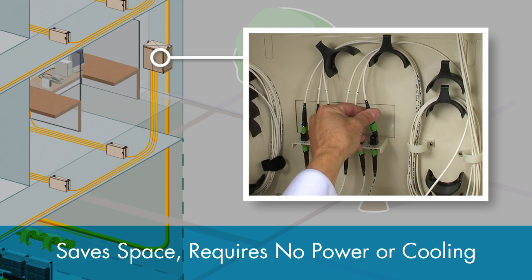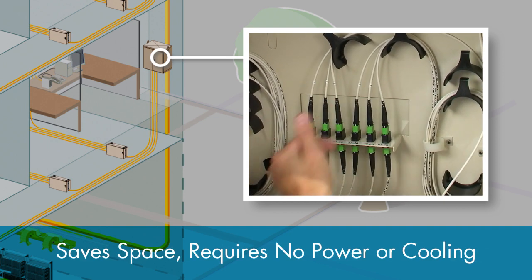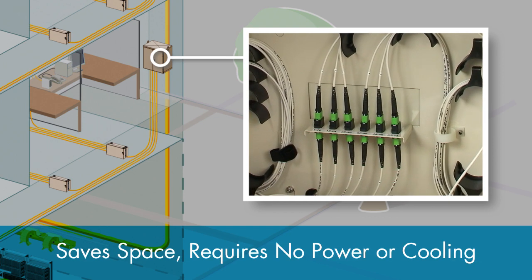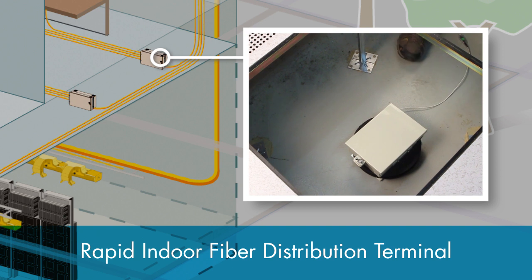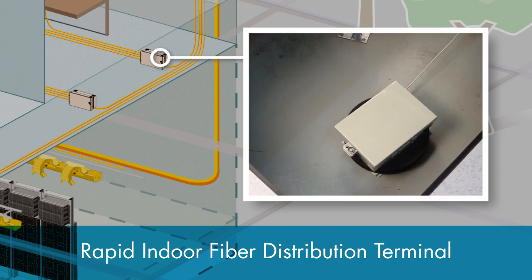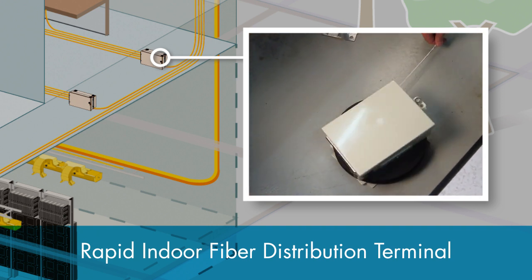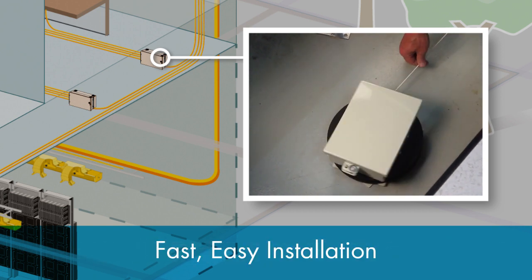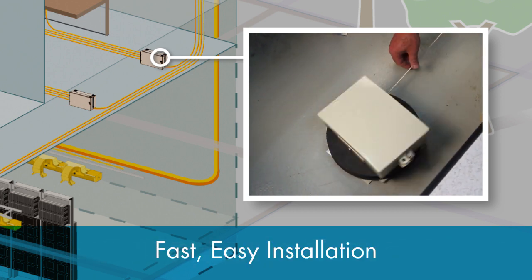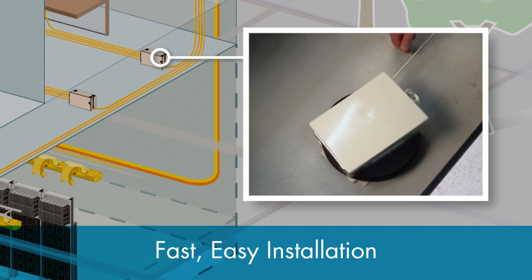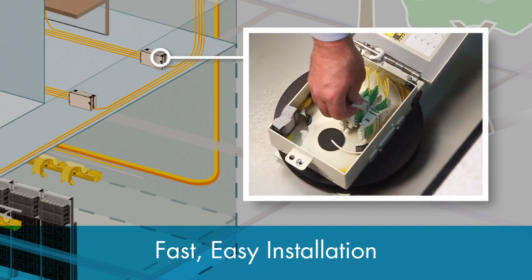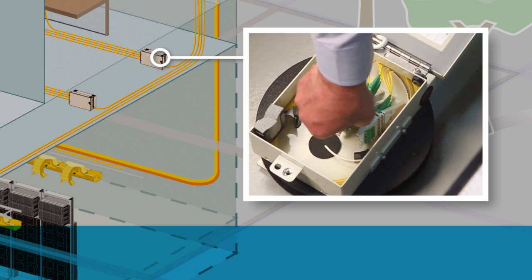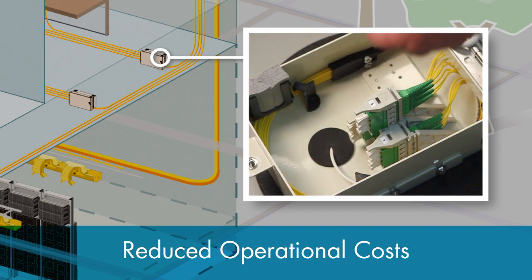It is also wall-mounted, which saves valuable floor space in the IDF telco closet and requires no power or cooling. Optical LAN installations use CommScope's Rapid Indoor Fiber Distribution Terminals, or IFDTs, as consolidation points. By integrating cable payout systems with fast unspooling of up to 300 feet of cable from a single 6-by-9-inch wall box, these IFDTs save even more physical space by eliminating the need for separate cable assemblies, splice cases and boxes.